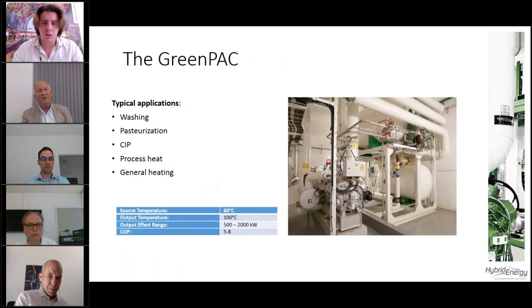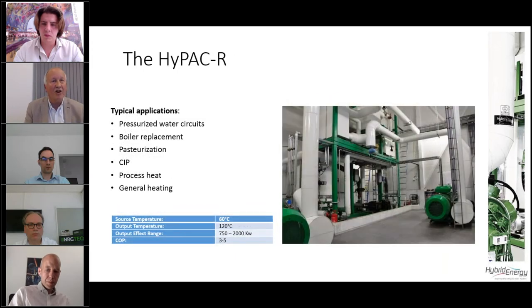The GreenPAC, which is the one that has been installed at Tine Bergen, have the typical applications, as you can see here, for dairy, and normally has source temperature 60 degrees and up to 100 degrees, and a power range of 500 to 2 megawatts. And the COP, depending on the operational conditions, are in the area of 5 to 8. The HyPAC-R have the typical applications for the dairy, and it can bring an output temperature up to 120 degrees, capacity range 750 to 2 megawatts, and a COP level at 3 to 5.